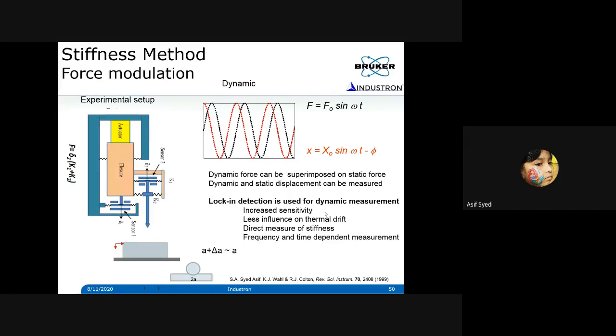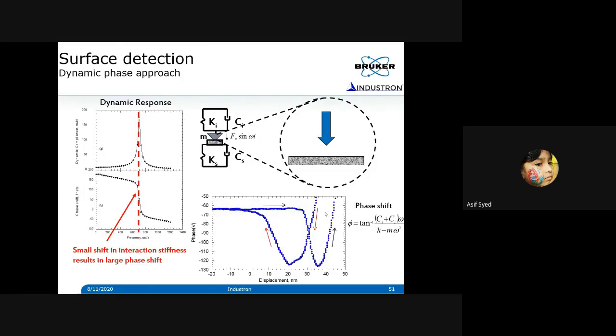For example, when you do this on an elastic material, there won't be any phase shift between the force you apply and the displacement you measure. The phase shift will be zero. But viscoelastic material tends to have a phase shift. The degree of phase shift gives you an idea of the viscosity of the material. This is something that I developed during my postdoc work at Naval Research Lab that was later commercialized at Hysitron. Using this approach, you can modulate the tip, which means you are applying a sinusoidal force to the tip, bringing the tip close to the surface and trying to measure whether there is any phase shift between the tip and the sample. If you see a phase shift, it's mainly due to some kind of attractive forces. For example, when you run this tip closer to resonant frequency and bring the tip closer to the surface, any interaction will shift this phase to either the right or the left, depending upon whether you have an attractive interaction or a repulsive interaction.